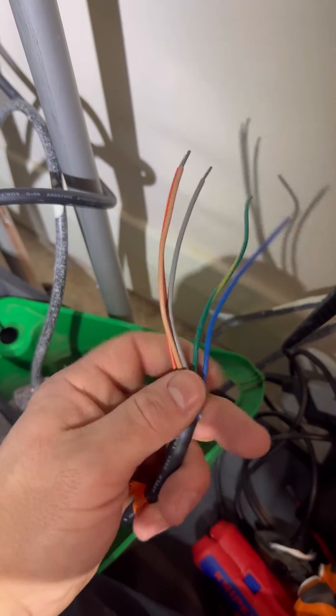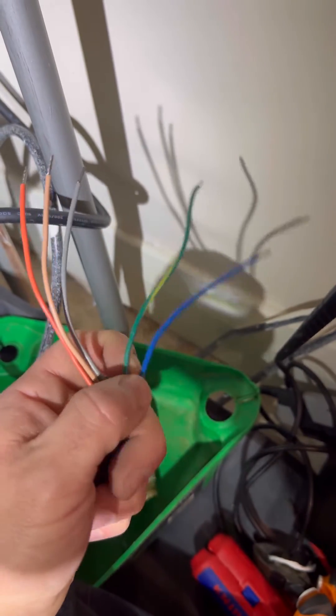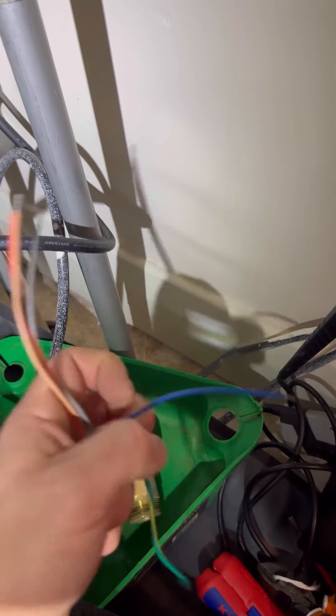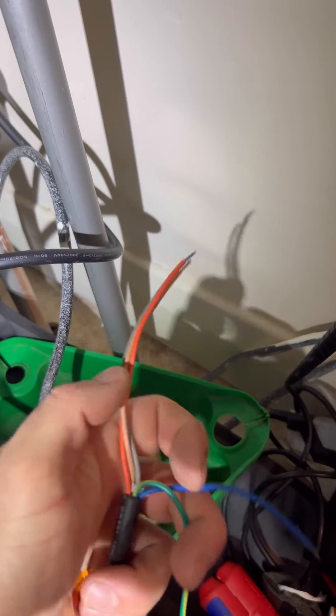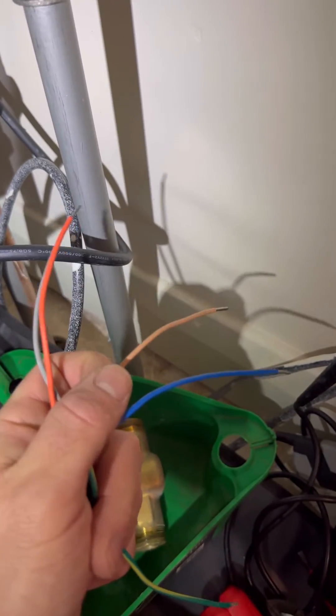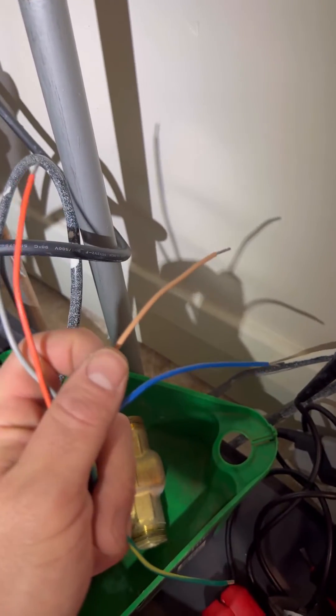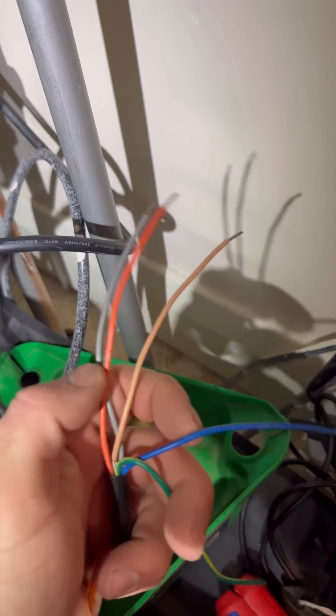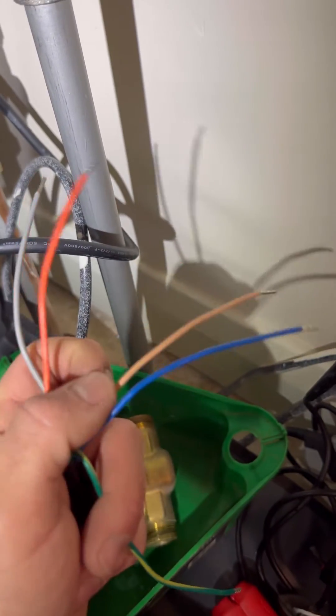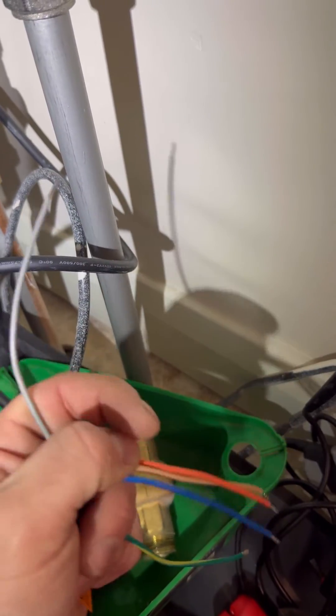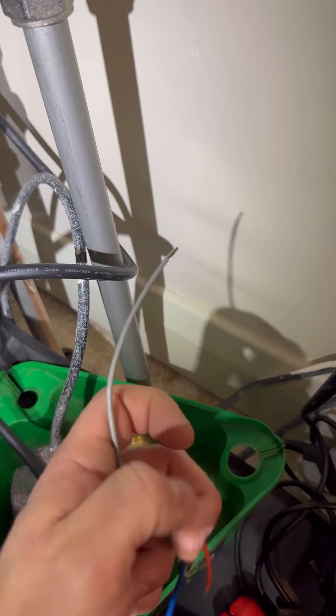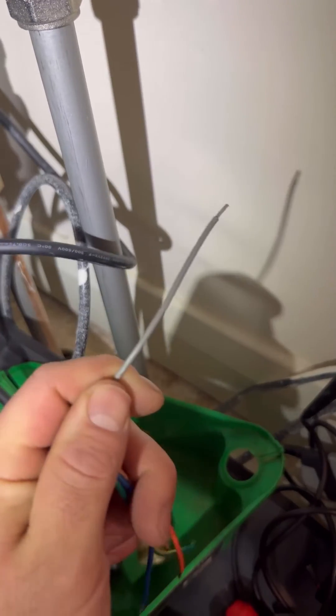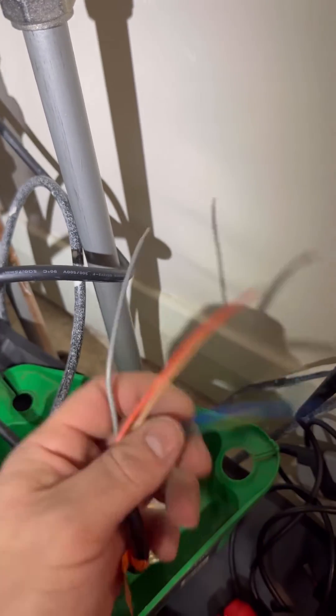Two-port valve, five cables. Neutral, your brown is your call from your room stat or cylinder stat. The orange is your feedback to the boiler to fire the boiler once the microswitch has been made, and gray is permanent live.